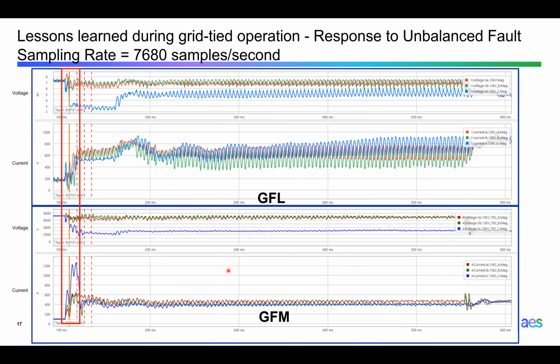This is another lesson learned for us here. This was a response between grid following inverter and grid forming inverter, and this was due to an unbalanced fault. We have high-speed digital fault recorders installed around the island, and we picked up this record. The sampling rate of the high-speed digital fault recorder that we have is 7,680 samples per second. You'll notice here in this top blue rectangle, we've got our grid following inverter voltage and current, and on the bottom, we've got grid forming voltage and current. To look at the differences here, we had a C phase to ground fault, the initial fault.